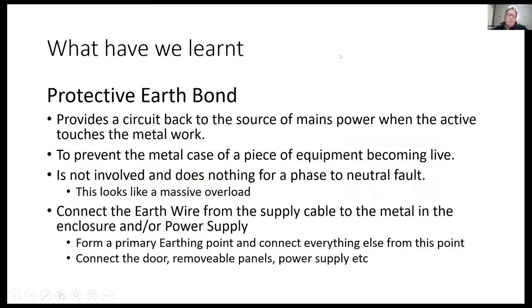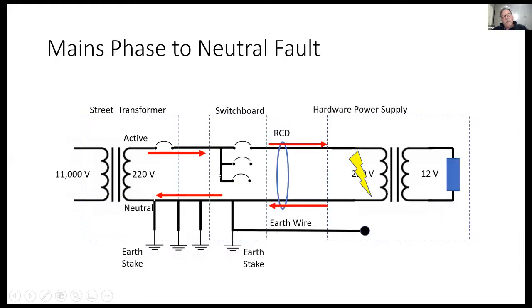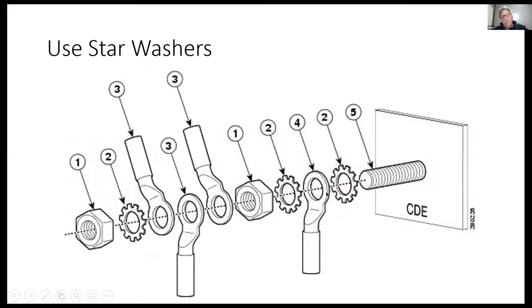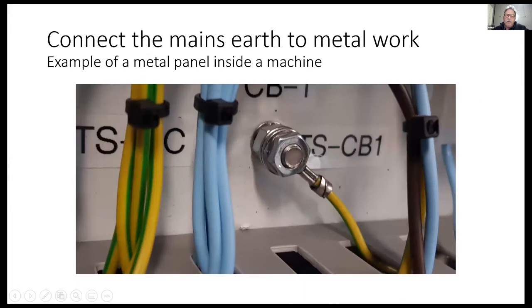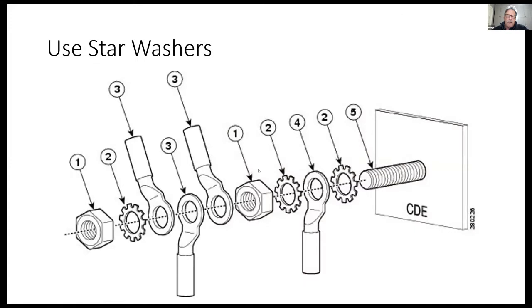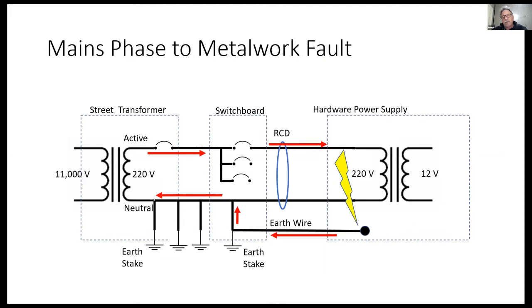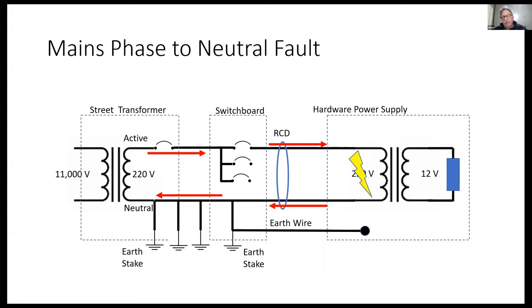So what have we learned here? Well, we've learned that a protective earth provides a circuit back when the active touches the metalwork. It prevents the metalwork becoming live. Protective earth is not involved when you've got a phase to neutral fault. That just looks like a massive overload. And the other thing is, coming right back here to this concept of a stud, if you put one connection like I've done here, you can then have multiple connections out to all the panels and everything. So you have one central point that you call your protective earth. And you can do the same sort of thing on the secondary of a power supply: if you connect the 12 volt negative of a power supply, you can create this concept of an earthing point.